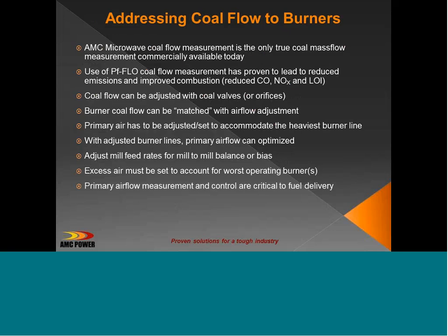The coal flow technology is probably the newest thing that we have, and I say new to the power industry, is 10 years. We've had this out almost a full 10 years. We re-engineered it to what we call PfFLO 3 about 7 years ago, where we took the technology that originally came from Germany. We licensed it, we re-engineered it with some of our customers in mind, and have come out with it again as PfFLO 3. It's a microwave technology for measuring mass, and we use cross-correlation for measuring speed of fuel. And when you multiply the mass by the speed, you get mass flow.